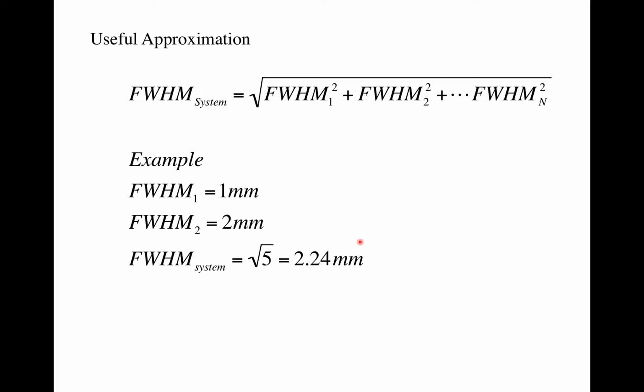And so in our system, we have the sampling grid, the fact that those 1 millimeter detectors have a width and are integrating X-rays over that 1 millimeter. That's a source. That'll be one of these. We have the ramp function plus the window, whether it's a Hanning or cosine or something like that. That'll be one of these, right? And then the spot size will be one of these as well. And so the net result is the cascade of all those things.